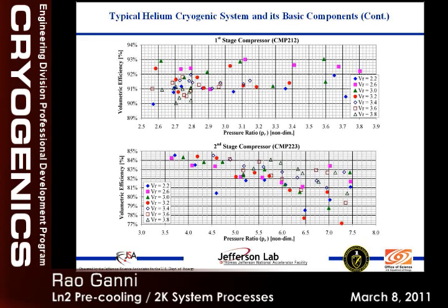At SNS, with the time we got and with the instrumentation, we did some testing varying the built-in volume ratio and the pressure ratios, and we measured the volumetric efficiency of the first stage and second stage. You can see the influence of the built-in volume ratio. These characteristics won't be available to us from the screw manufacturers, because none of them ever have the luxury of these test beds. So we're trying to generate this information so that we all can benefit from it.